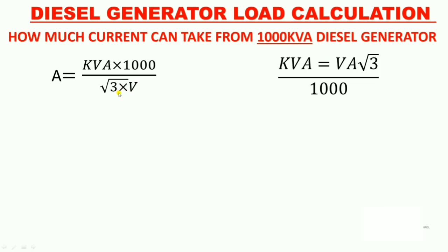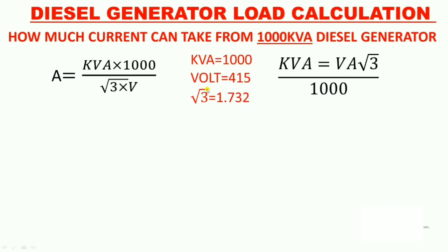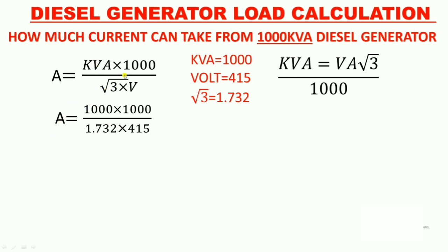Now let us start the calculation. First understand which values to put into this formula. kVA is equal to 1000, and the voltage generated by the diesel generator is 415 volts, and the √3 value is 1.732. Now put those values into the formula: Ampere = (kVA × 1000) / (√3 × V) = (1000 × 1000) / (1.732 × 415).